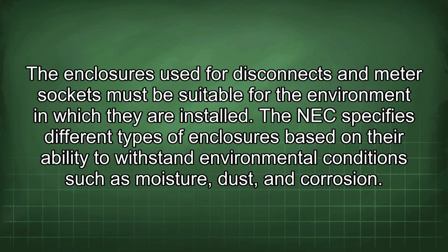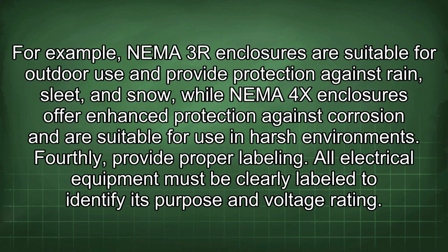Thirdly, use appropriate enclosures. The enclosures used for disconnects and meter sockets must be suitable for the environment in which they are installed. The NEC specifies different types of enclosures based on their ability to withstand environmental conditions such as moisture, dust, and corrosion. For example, NEMA 3R enclosures are suitable for outdoor use and provide protection against rain, sleet, and snow, while NEMA 4X enclosures offer enhanced protection against corrosion and are suitable for use in harsh environments.